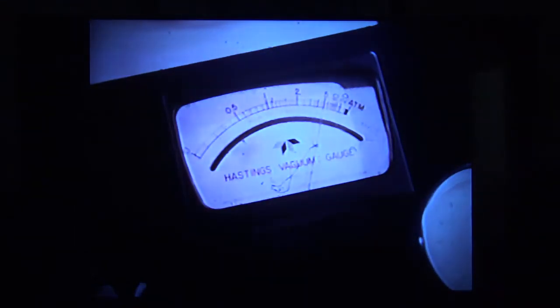Close the pump blank-off valve and watch the electronic vacuum gauge for 1 minute. The meter should not indicate a rise of more than 5 millimeters. If the gauge rises more than 5 millimeters in 1 minute, the system has a leak which must be repaired. Open the pump blank-off valve and continue to operate the vacuum pump for an additional 20 minutes.